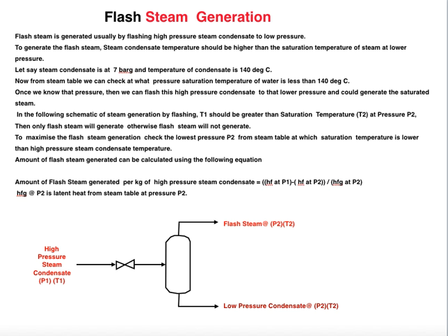Looking at this schematic of flash steam generation: high pressure steam condensate passes through a control valve where pressure is dropped to a lower pressure. The condensate gets flashed in a flashing vessel — steam is separated and comes out from the top of the vessel, while low pressure condensate comes out from the bottom of the flashing vessel.